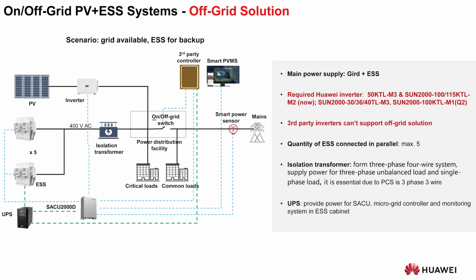So you've got your PV panels, your inverter, which is connected to your on-off grid switch, which is then connected to your critical loads and your common loads, okay? And this is how you distribute the loads here. In between here, you'll have to have an isolation transformer, which is a 400 volt isolation transformer. You can have a max of 5 ESSs connected here. In addition, you also need a UPS for your microgrid controller, okay? You'll also have your power sensor here.